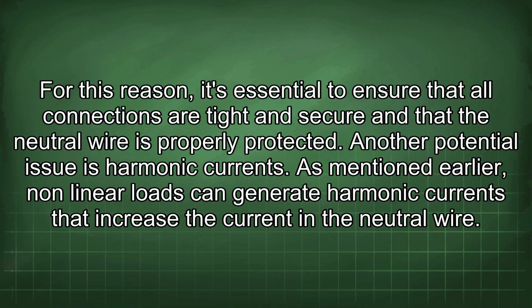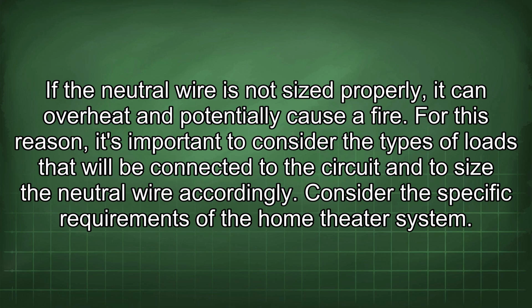Another potential issue is harmonic currents. As mentioned earlier, nonlinear loads can generate harmonic currents that increase the current in the neutral wire. If the neutral wire is not sized properly, it can overheat and potentially cause a fire. For this reason, it's important to consider the types of loads that will be connected to the circuit and to size the neutral wire accordingly.